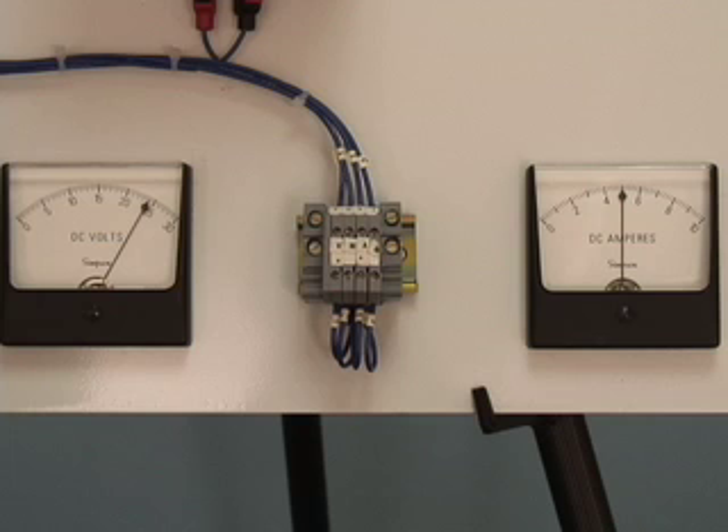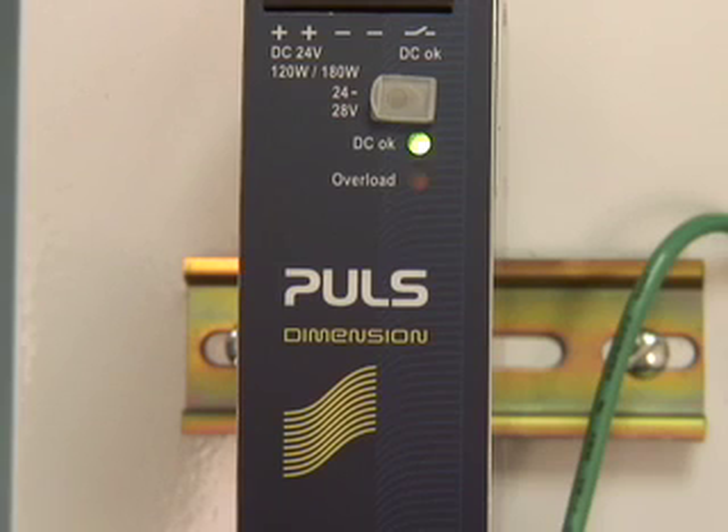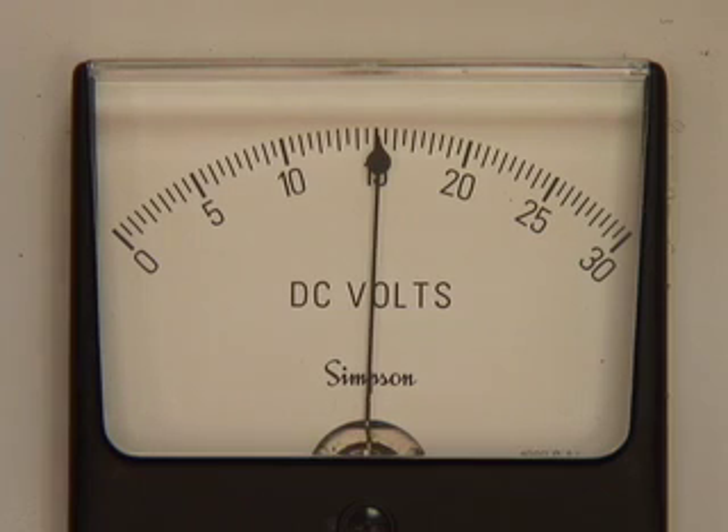However, if a locked rotor condition occurs where the inrush current does not return to normal, we can watch what happens to the output voltage and current. After 4 seconds, the power supply tapered back the output voltage and current, and the overload light turned on. But once the overload condition is eliminated, the power supply returns to normal operating conditions.